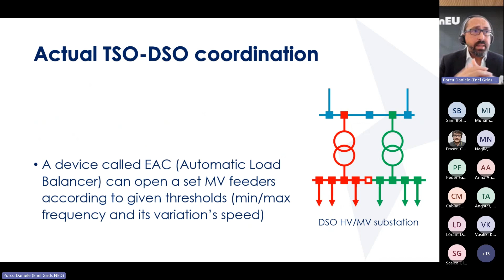So this is the schema of the high voltage, mid to medium voltage substation of the DSO. And actually, the main device in the DSO premises is called EAC. It's an automatic load balancer that keeps analyzing the frequency and also the time derivative of how the frequency is changing. And there are a set of rules and a set of medium voltage feeders that can be opened to prevent major disruption in the grid.